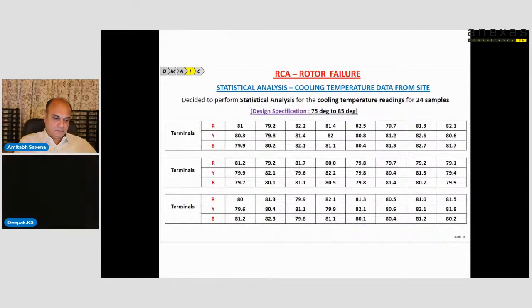After the corrective action was completed, the customer wanted us to do the statistical analysis on this. The readings were taken of 24 samples. Our site engineer visited there. He took the samples of R, Y, and B terminals. There are 24 readings. The design specification should be 75° to 85°. It is well within the specification. This was the reading taken from site after the corrective action.